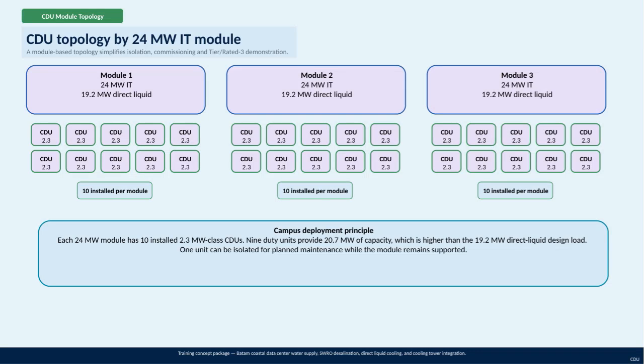Here we have the CDU module topology based on a 24 megawatt IT module. This modular approach offers several advantages, particularly in simplifying isolation and commissioning processes, as well as supporting Tier 3 or Rated 3 demonstration requirements. The training concept package focuses on integrating multiple advanced systems at the Batam Coastal Data Center, including its water supply, seawater reverse osmosis desalination, direct liquid cooling, and cooling tower operations. Each module, such as Module 1, 2, and 3, is designed around 24 megawatts of IT capacity with 19.2 megawatts dedicated to direct liquid cooling.